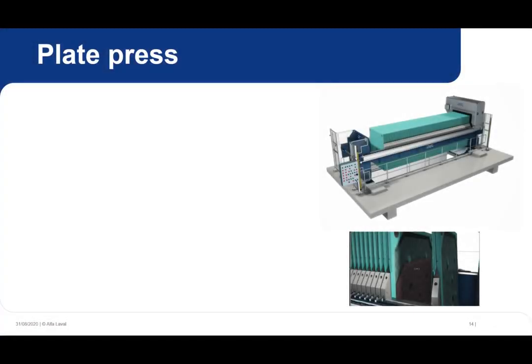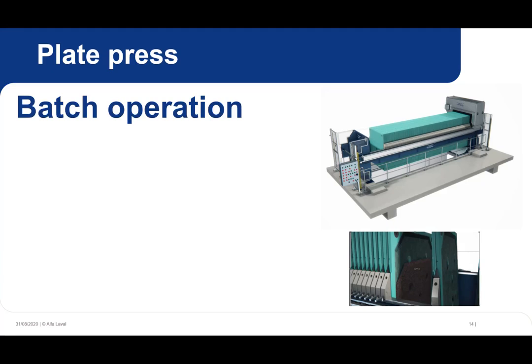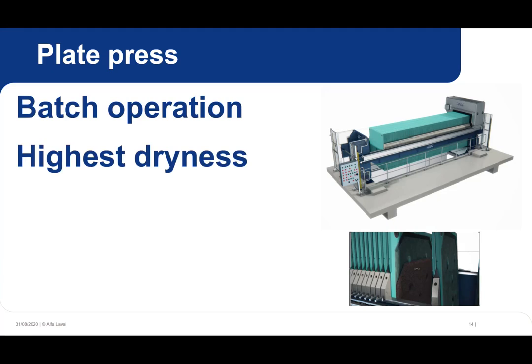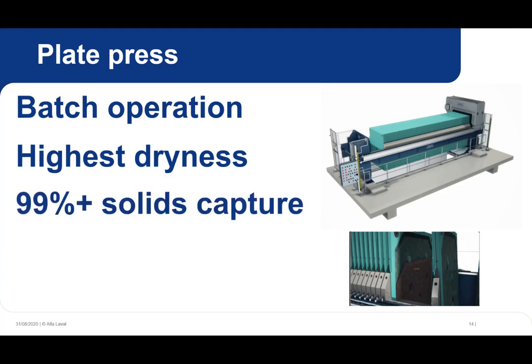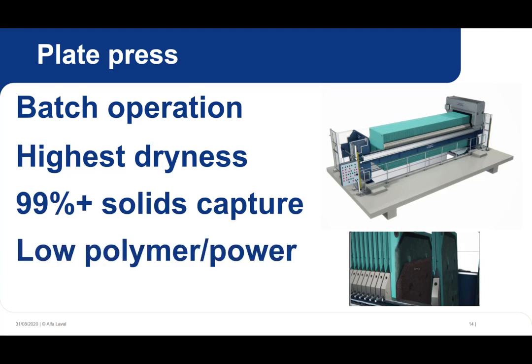A plate press is suitable for certain municipal applications, such as waterworks residuals, or industrial applications depending on the needs and sludge properties of the facility and where batch operation is acceptable. A plate press delivers the highest dryness of what we are discussing today. In municipal applications, dry solids can be up to 40%. Dryness of 90% or higher on some industrial applications is also possible, with a solids capture rate greater than 99% in most cases.